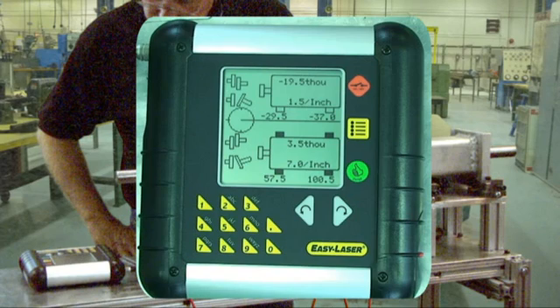Starting at the top of the screen the first number shows the amount of offset in the vertical plane measured at the coupling which is negative 19.5 thou. The next number is 1.5 thou per inch of angular error again measured at the coupling.